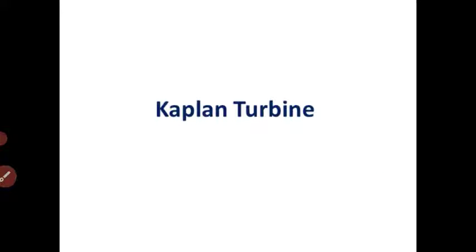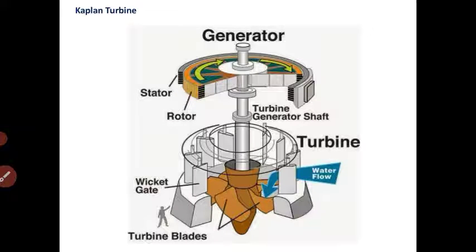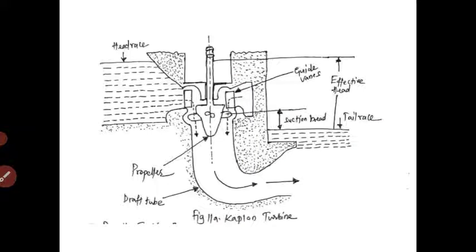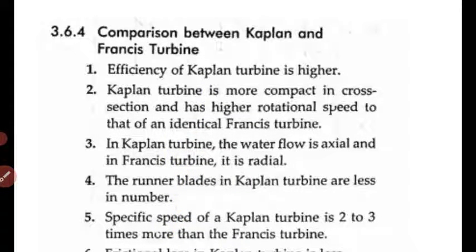Next is the Kaplan turbine, which is also a reaction type. Comparing Kaplan and Francis turbines: both are reaction turbines. The efficiency of the Kaplan turbine is higher. The Kaplan turbine is more compact in cross section and has a higher rotational speed than an identical Francis turbine.